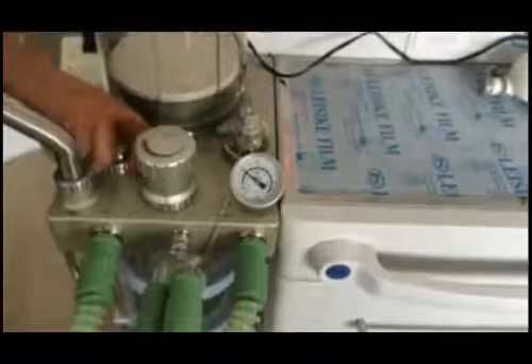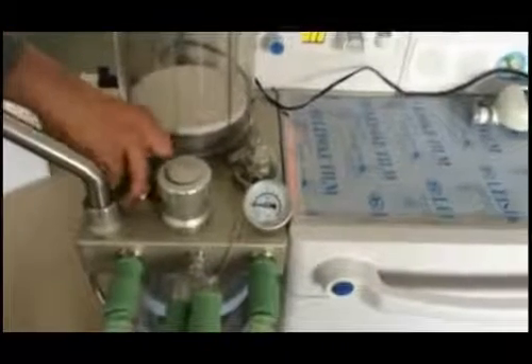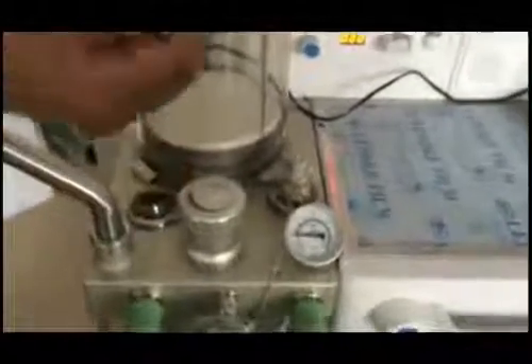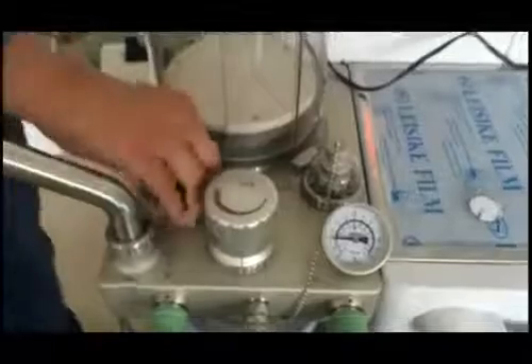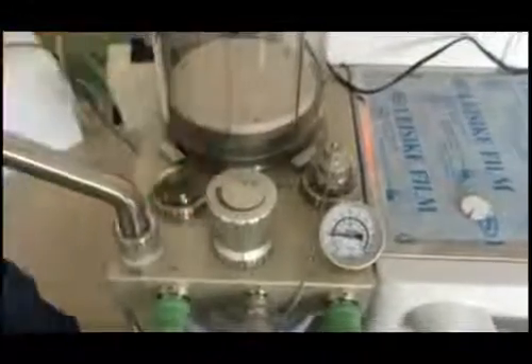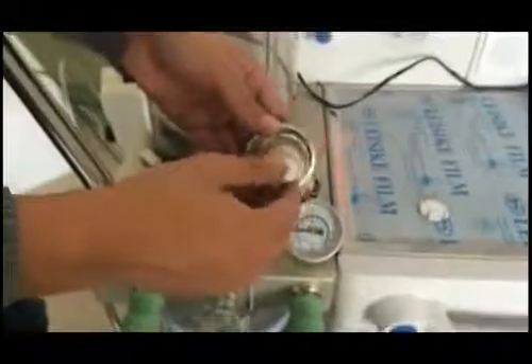This is the expiration valve. This is the inspiration valve. Remove the covers first. After removing the covers, please remove the disc. This is the disc and this is the disc holder. After removing it, please reinstall this cover. Do the same for the inspiration valve. You do not need to remove the O2 sensor.